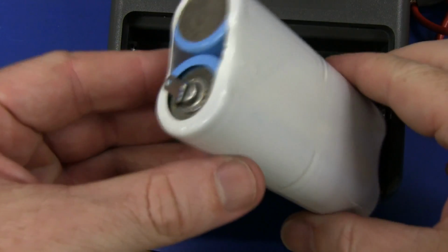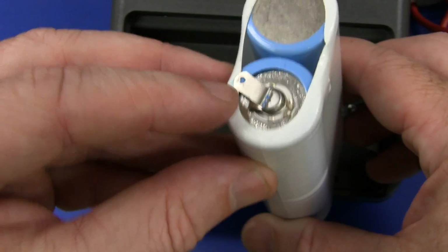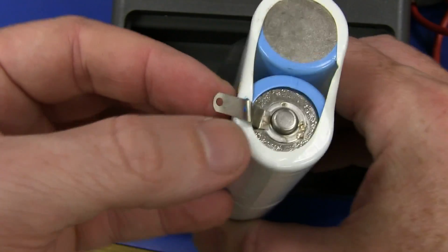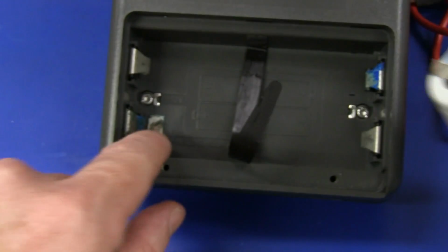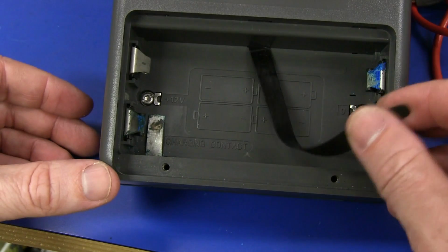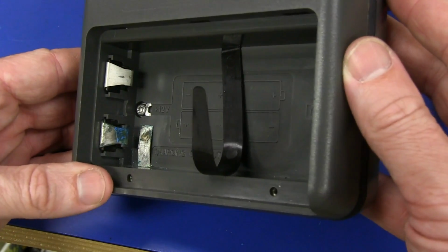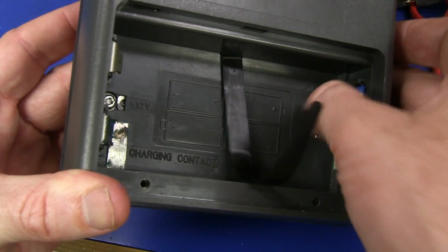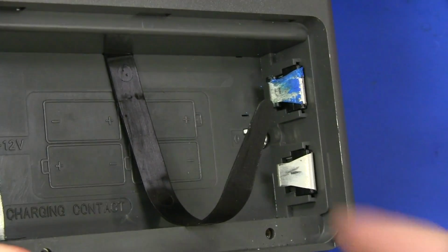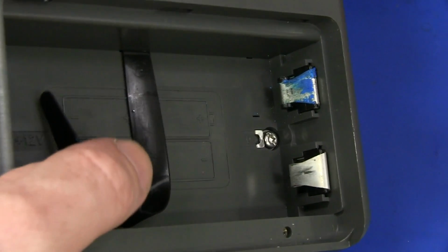And here's the battery pack in it, and I think I may have discovered an issue. The charging tab under there was folded up. It's supposed to be folded under like that, so it makes contact down in there, but it's a rechargeable battery pack, and it didn't do that. And we've got a bit of corrosion on the contacts, so I'll clean that. Ugh, it's blue. Anyway, clean that up, and I reckon I'd be very surprised if this sucker doesn't work and is fully in cal.